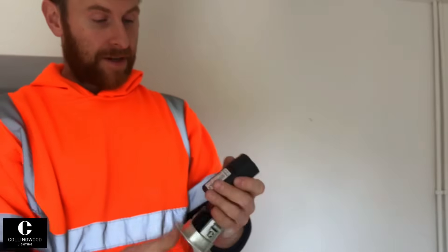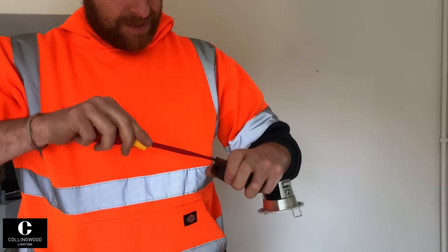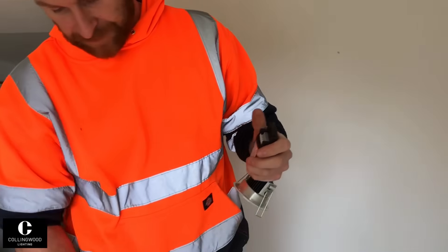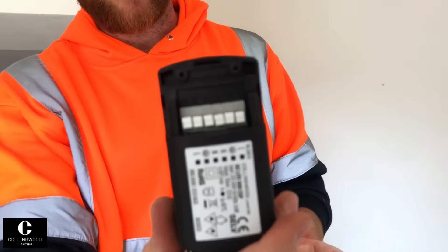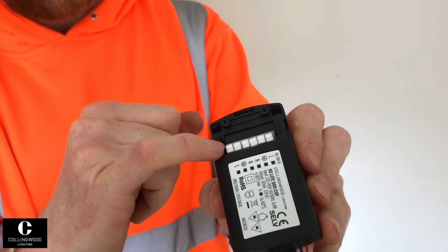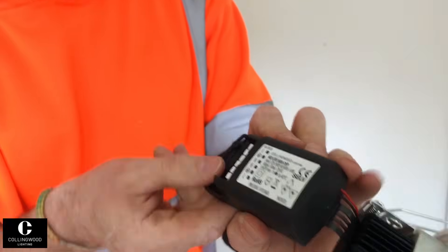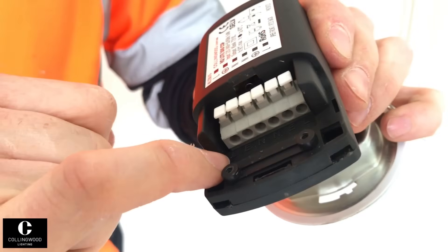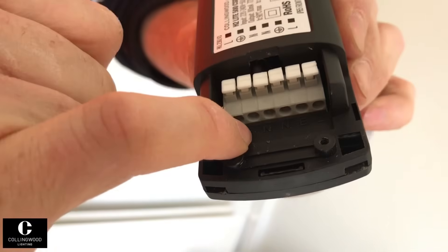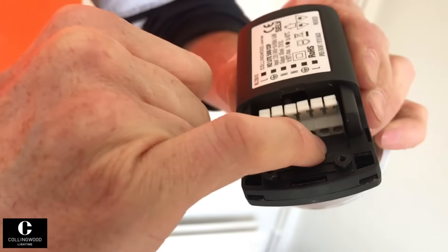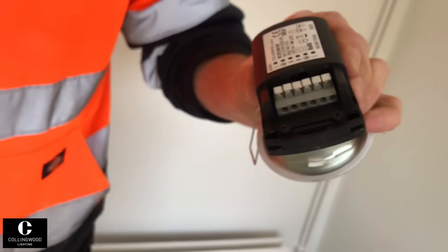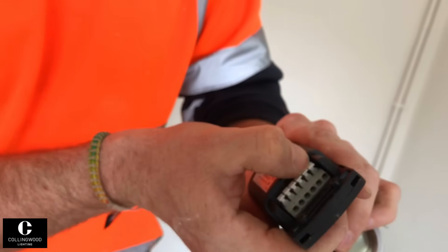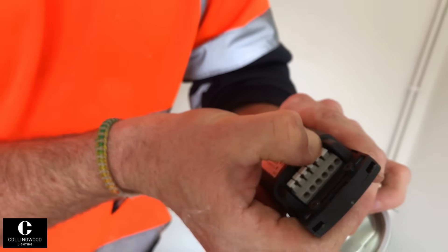So let's have a go at fitting it. Take this off, comes apart nice and easily. As you can see, that's slightly different on these ones compared to some of the other downlights. They're just push fit fittings. Your line, your earth, your CPC goes in there, your neutral, and then it's your neutral, your CPC, and your line in there. They're just simple push fit fittings. Hopefully they'll be as simple as just literally pushing it down with your thumb and pushing the cable in, or I'll have to push down with a screwdriver. I don't quite know yet.